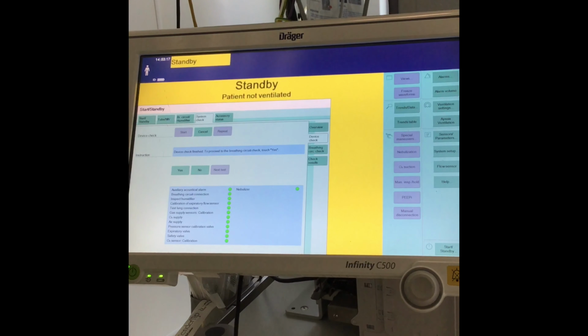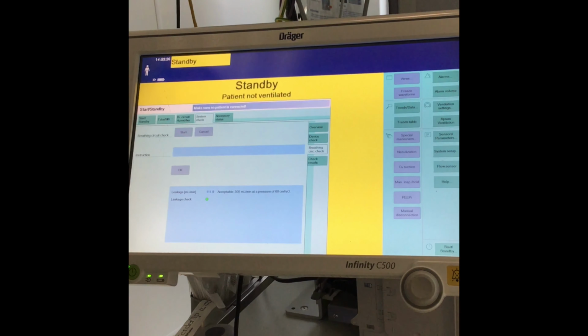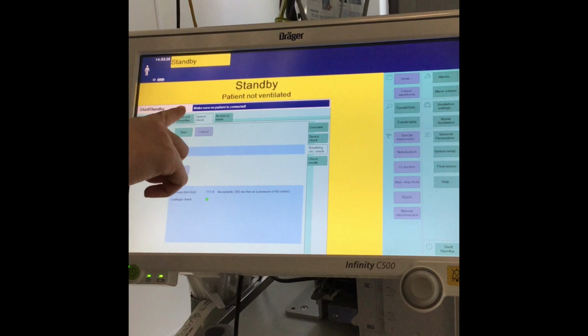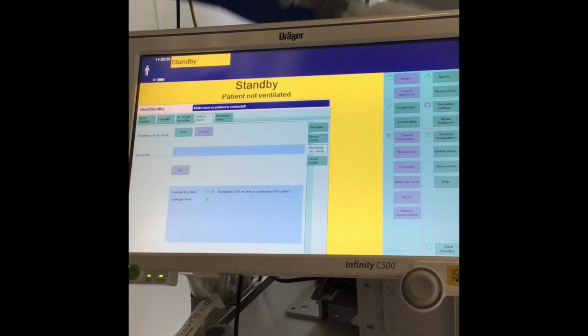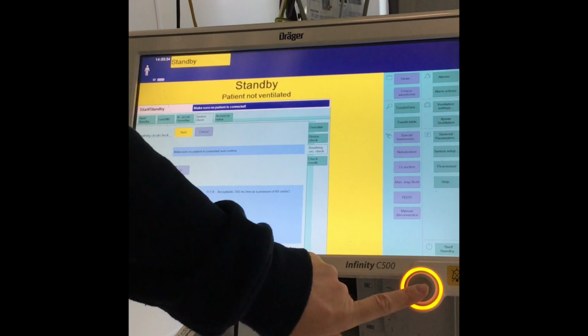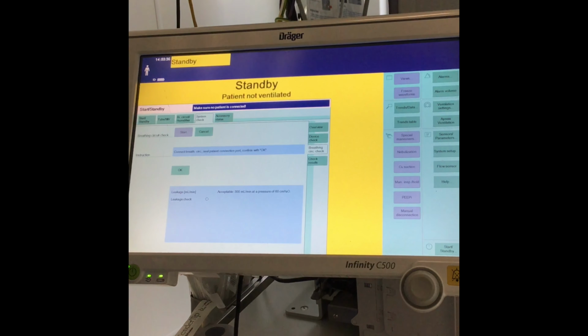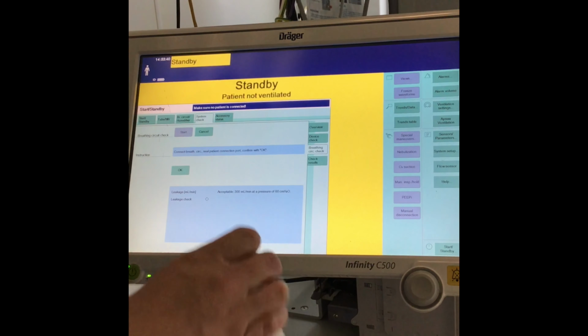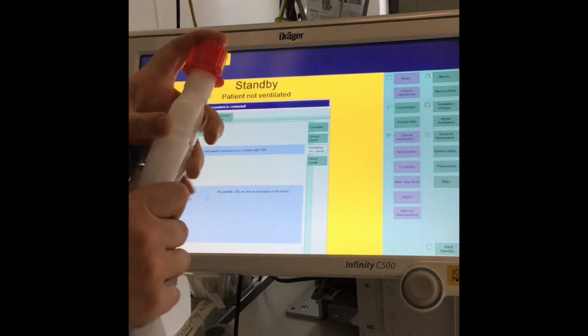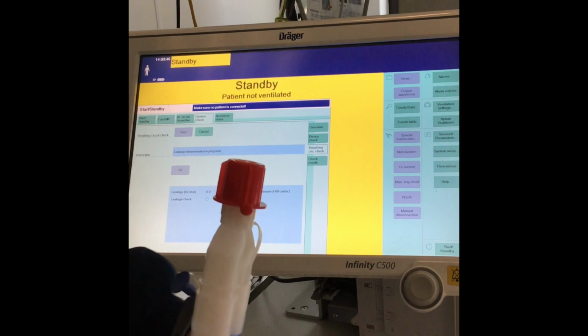The breathing circuit check needs to be completed before use and at any point of ventilator tubing change. I'm just going to hit yes. Saying here, make sure no patient is connected. We obviously don't have a patient connected, so we're going to hit start and we're going to confirm it with the rotary knob. Saying to connect the breathing circuit and seal patient connection port and then hit OK. So I'm going to put the bung on the end of the tubing, hit OK.